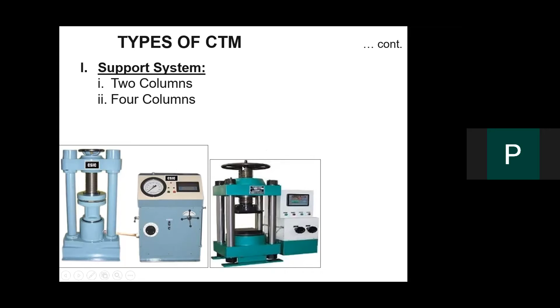To make the system's exact central axis or the CG of the machine come at the center of this area of the cube, so that my machine will give axial loading, is very difficult with 2 columns. So they changed into 3 and ultimately came to 4 columns. This way I can easily make my arrangement with supporting systems, put wedges, make the system horizontal, and make the load indicator or axial load calculation perfectly centered. So this is the upgradation from 2 to 4 columns.